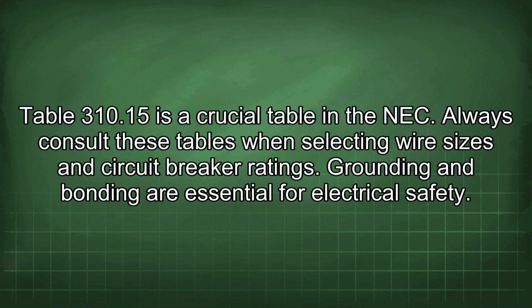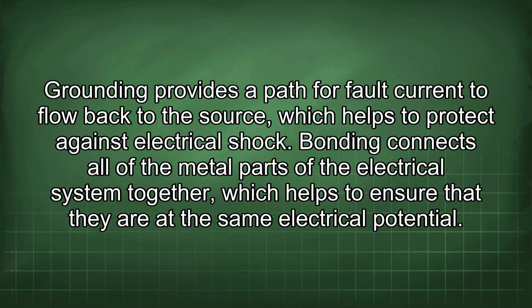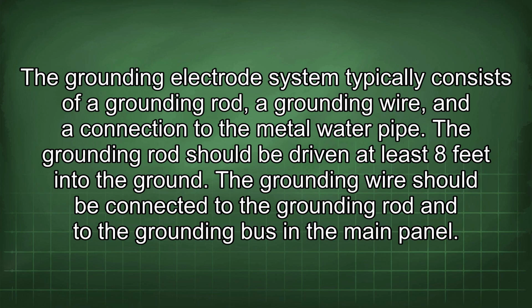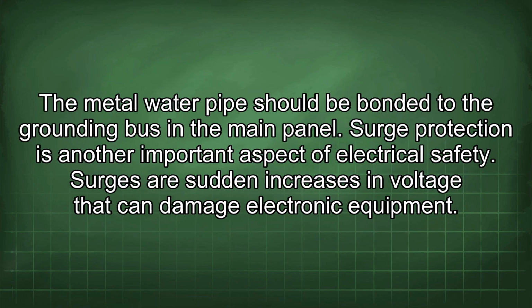Grounding and bonding are essential for electrical safety. Grounding provides a path for fault current to flow back to the source, which helps to protect against electrical shock. Bonding connects all of the metal parts of the electrical system together, which helps to ensure that they are at the same electrical potential. The grounding electrode system typically consists of a grounding rod, a grounding wire, and a connection to the metal water pipe. The grounding rod should be driven at least 8 feet into the ground. The grounding wire should be connected to the grounding rod and to the grounding bus in the main panel. The metal water pipe should be bonded to the grounding bus in the main panel.